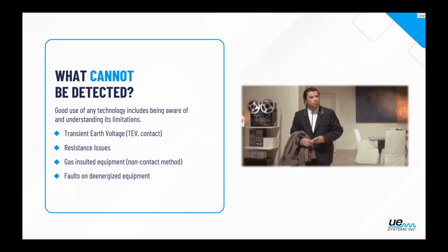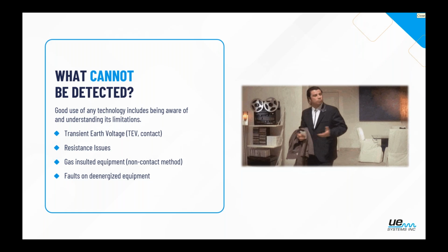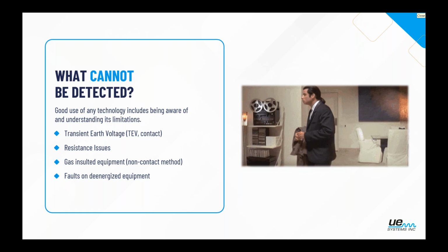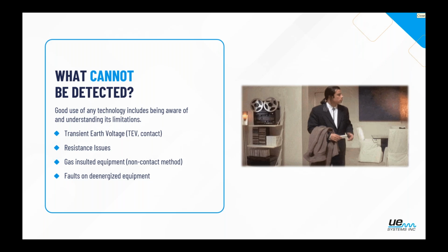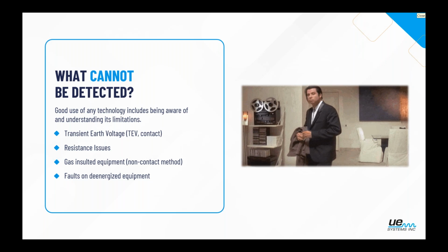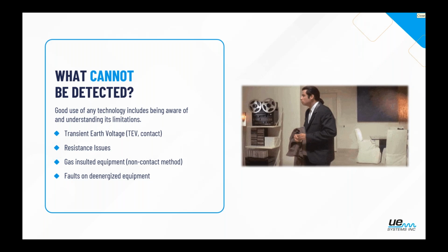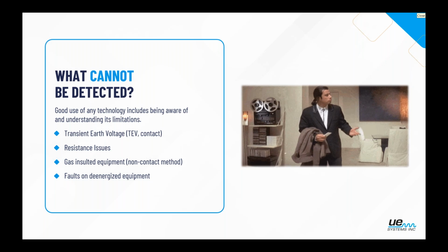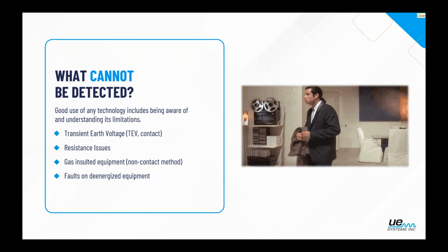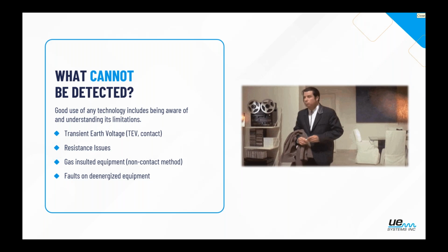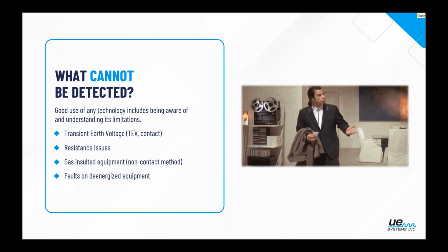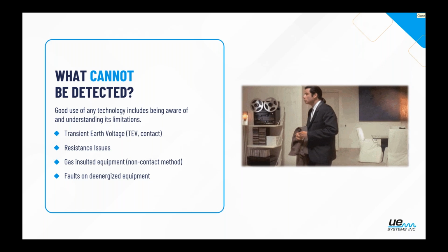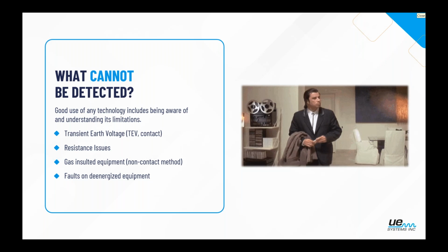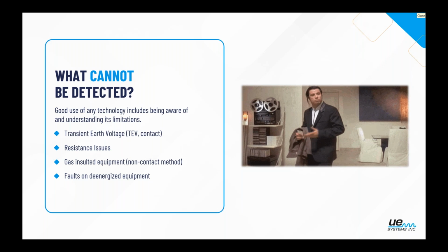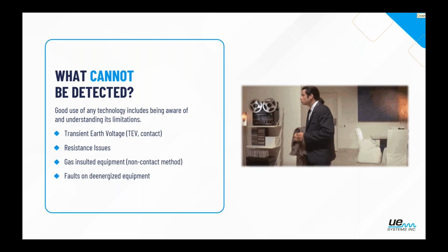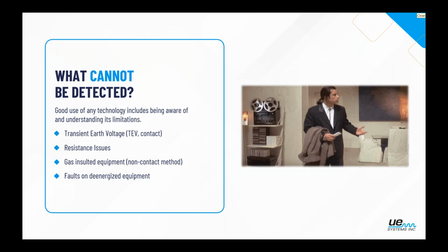So what can't be detected? I always get these questions. I always like to make sure people are aware that just like with infrared, there are things that cannot be inspected through ultrasound. There are very specific issues that we do not look for. We will refer to other applications for it. The first one is transient earth voltage, often just referred to as TEV. While there are ultrasonic based devices out there to inspect for this, they are very specialized pieces of equipment and they are contact based. So I would never look for TEV through an ultra probe or an acoustic camera.